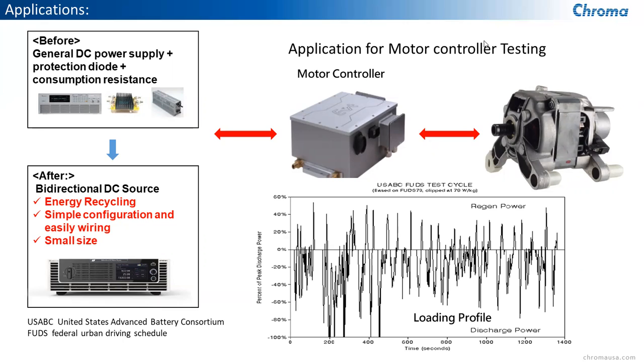A typical test setup now is purely dissipative. You have a resistive load bank that just burns up the power during the braking, to allow that power to get back to be dissipated from the motor when it's in braking. When you're driving it, it's driving it purely from a DC source, and you also would need an external high voltage, high current diode to protect your DC source from energy being fed back to it. So none of that would be required for the 62,000D bidirectional DC supplies.